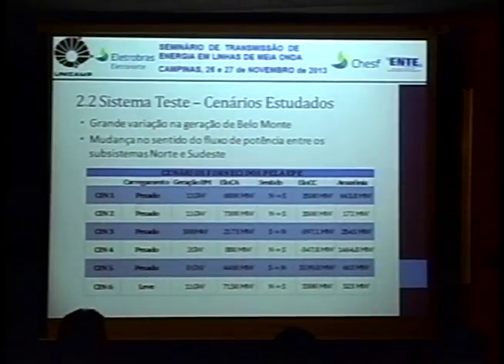The scenarios for the integrated system: we have 3 scenarios for heavy loads and 1 for light loads. The generation in Belo Monte would vary from 11 gigawatts down to 0, 2 gigawatts, 500 megawatts. So we have a broad variation in terms of generation in Belo Monte due to rainfall and the lack of reservoir in this hydraulic power plant.